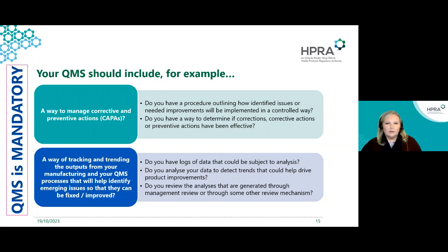Moving on to the final element of Article 10, Part 9, M. This section requires the manufacturer to use all the data collected throughout the life cycle of the product and from the implementation of the QMS for monitoring, measuring, and analysis in order to facilitate product improvement. To monitor, measure, and analyze, you need data, and for that, the QMS must be in constant use and not just there to fulfill the requirement of the MDR. The data collected can provide a roadmap to improvement by identifying trends and highlighting issues within current processes.